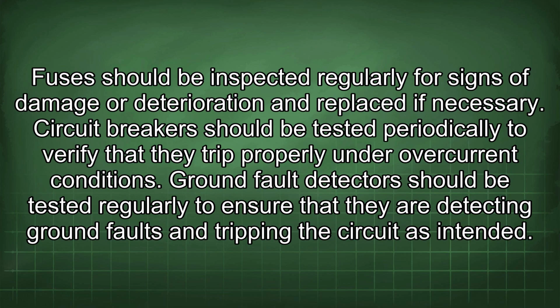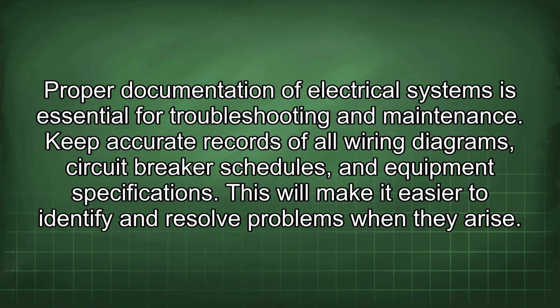Fuses should be inspected regularly for signs of damage or deterioration and replaced if necessary. Circuit breakers should be tested periodically to verify that they trip properly under overcurrent conditions. Ground fault detectors should be tested regularly to ensure that they are detecting ground faults and tripping the circuit as intended. Proper documentation of electrical systems is essential for troubleshooting and maintenance. Keep accurate records of all wiring diagrams, circuit breaker schedules, and equipment specifications. This will make it easier to identify and resolve problems when they arise.